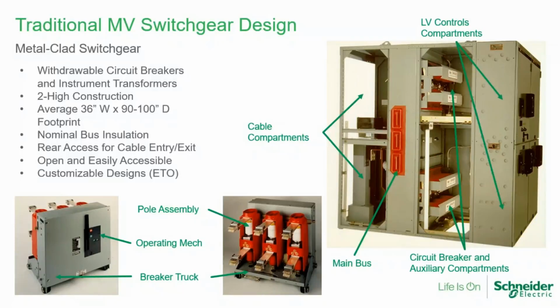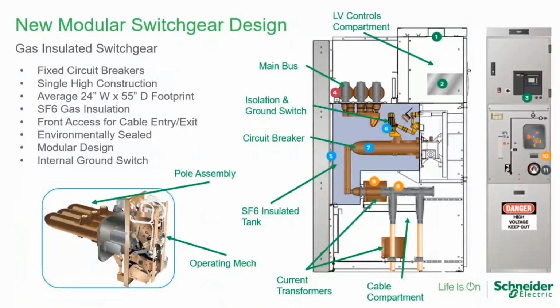Looking at the circuit breaker design, there are 3 main components: the pole assembly in the rear, the operating mechanism, usually in the front, sometimes in the bottom, depending on the manufacturer of the circuit breaker, and then the breaker truck in the bottom that makes it easy to roll the breaker in and out.